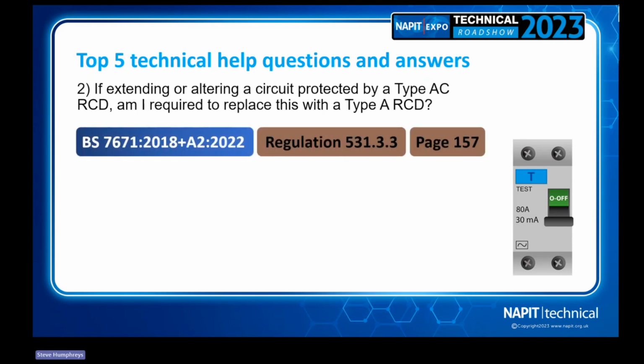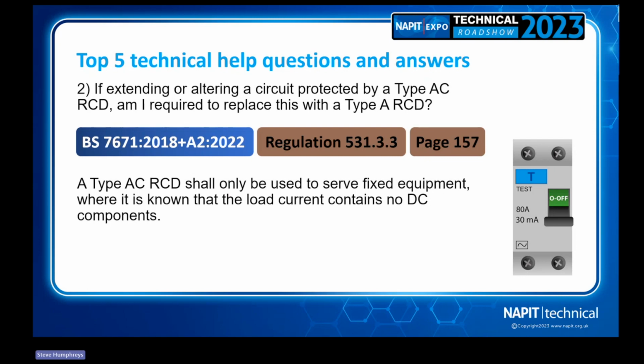Again, the regulation that points to this is 531.3.3 on page 157. And it says here, a type AC RCD shall only be used to serve fixed equipment where it is known that the load current contains no DC components. Now, this does obviously depend on the type of circuit and the equipment being used. So again, it's not necessarily a straight answer. For example, if a circuit is supplying socket outlets, then the customer can plug anything in. So in that situation, they're plugging in electronic equipment with DC components, and replacing that type AC RCD would be required. However, if the circuit is purely resistive, some fixed equipment, maybe a heater, something like that, then the AC type could potentially be left in place.